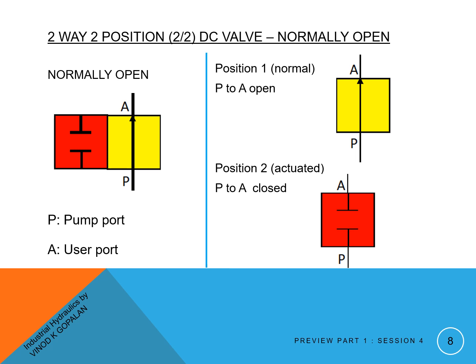You can also see two service ports, P and A, in the yellow colored portion. P is the pump port and A is the user port - meaning it connects to the user, which may be a hydraulic cylinder or a hydraulic motor. The number of ways is the number of service ports, so this is a two-way valve. There are two ways and two positions.